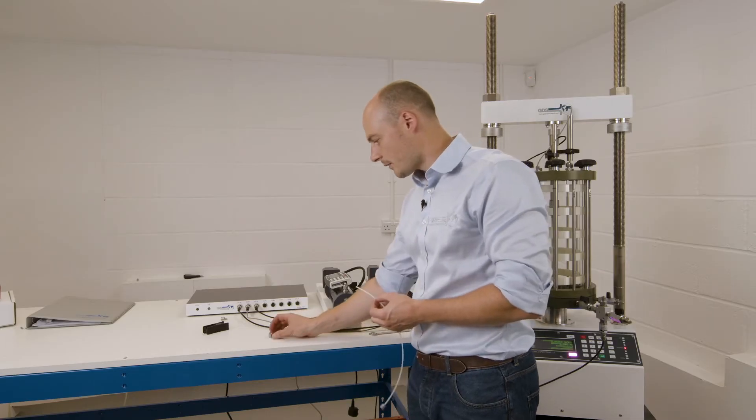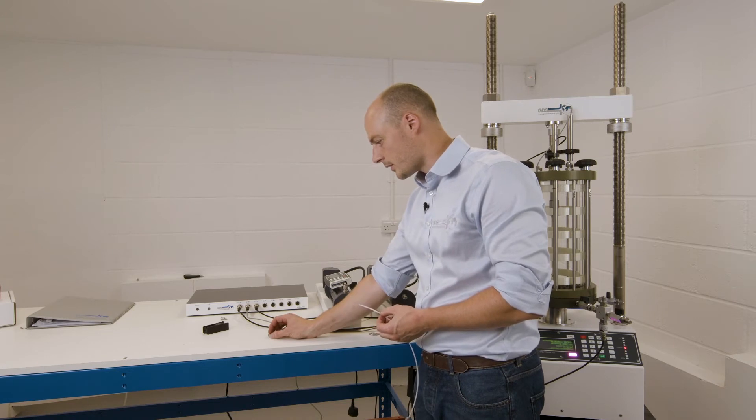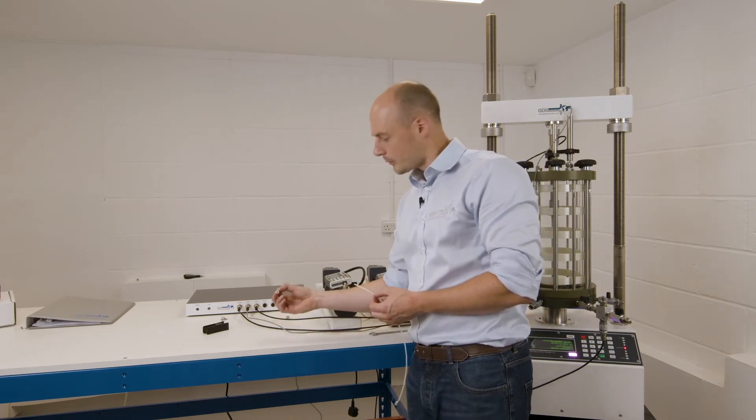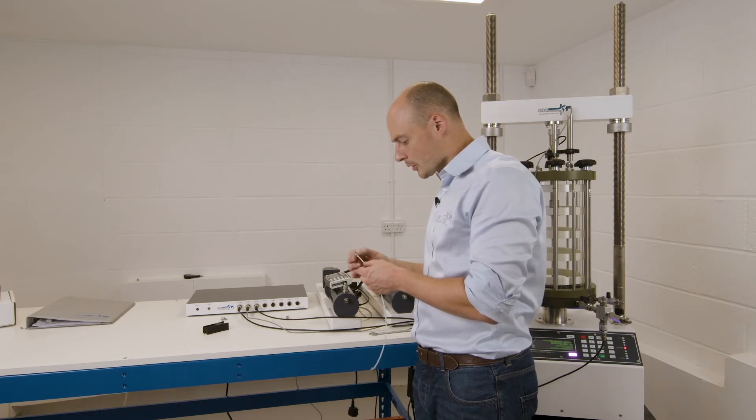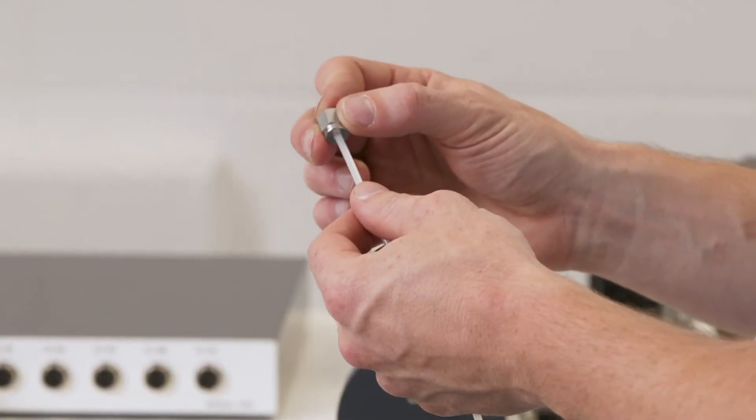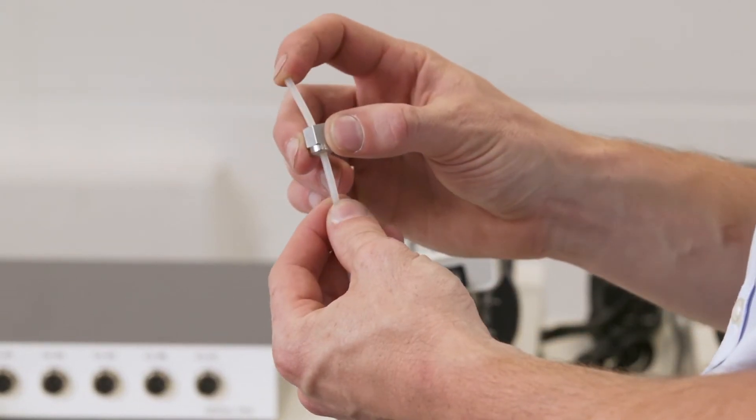Now we've cut our pipe, we can pick up our Swagelok connection. Put your finger over the end to stop all the internal fittings coming out. Push the pipe in, keeping the finger over the end until you feel the pipe push against your finger and then slide down.